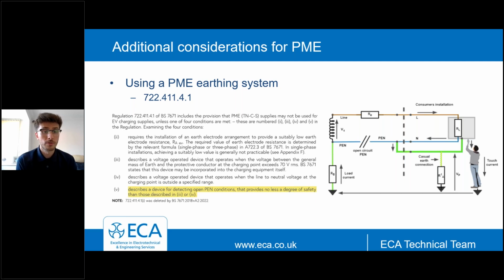Indent 4 describes a voltage operated device, but this time it looks at the line to neutral voltage, and the charging point should disconnect once this voltage goes outside of a specified range. Some EV charging equipment may use this to provide protection via indent 4. As mentioned, indent 5 is probably the most common measure applied to achieve compliance with this regulation. It describes a device for detecting open PEN conditions that provides no less degree of safety than those listed in indent 3 and indent 4.